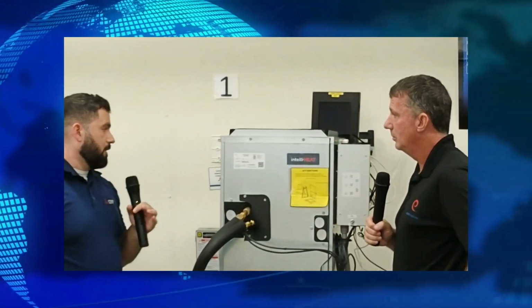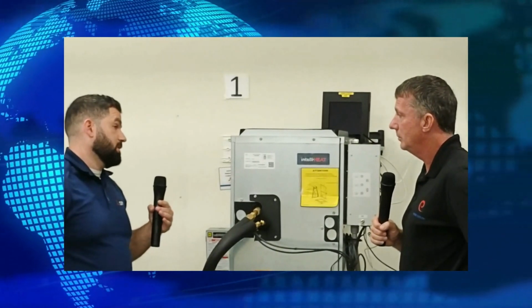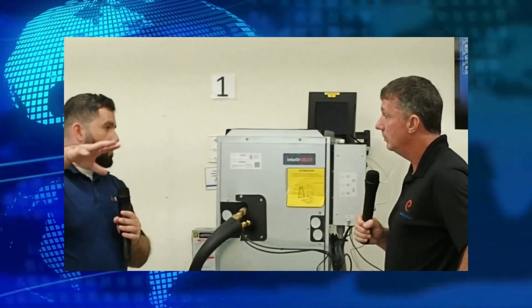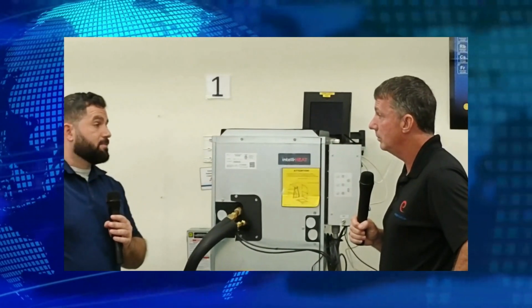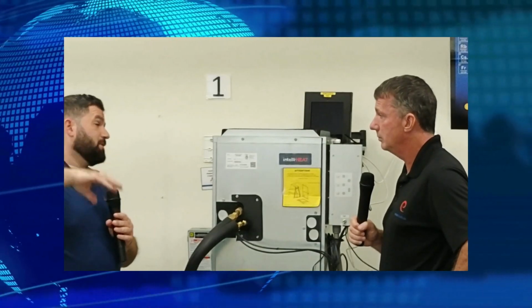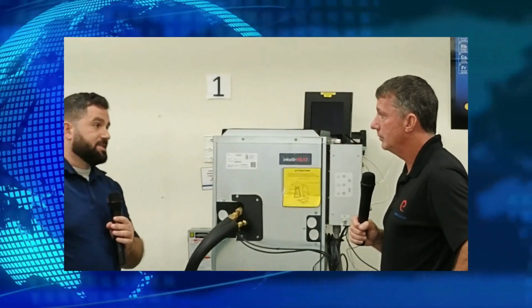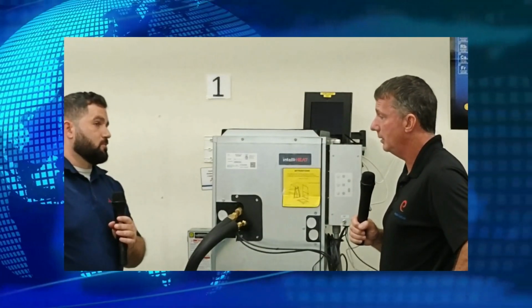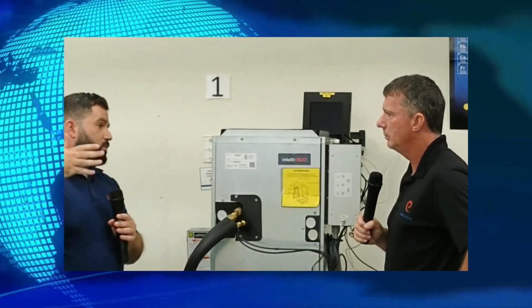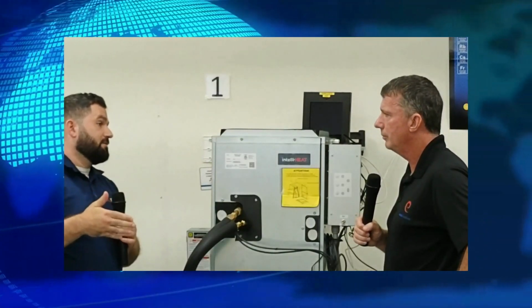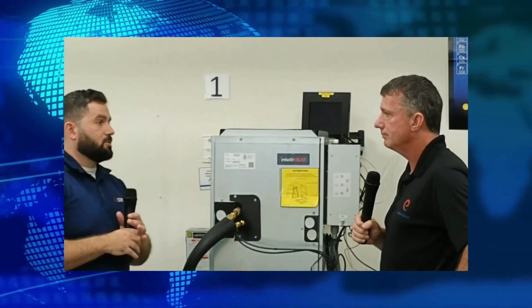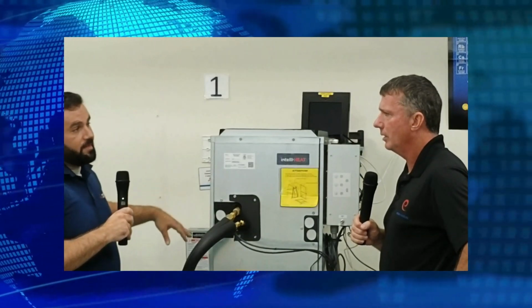The other really cool thing I like is our heat pump when we have our Hyperheat hooked up to this. Depending on what outdoor unit we choose, we get different balance point options. If we use a Hyperheat, we maintain 100% capacity down to -5 degrees, and we're still at about 73% at -13 degrees. So we can actually set balance points at -13 for when that Hyperheat unit just won't be able to keep up, and then stage that gas - prolonging the use of that fossil fuel.